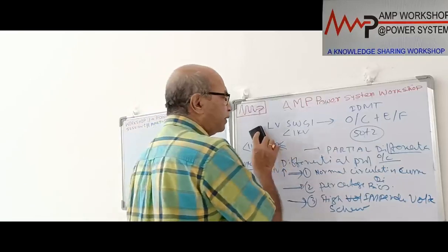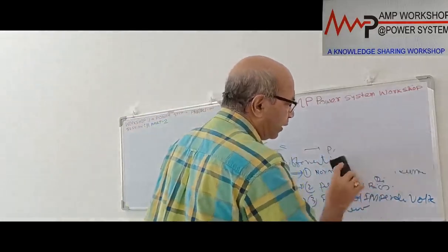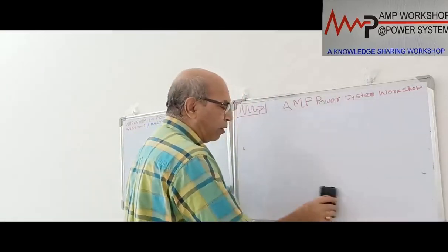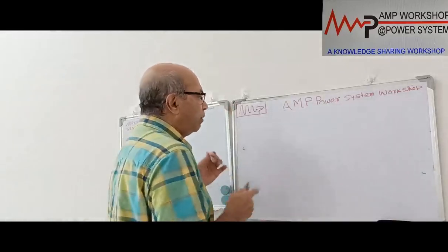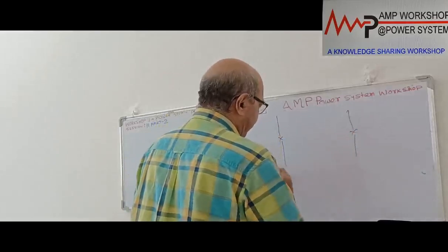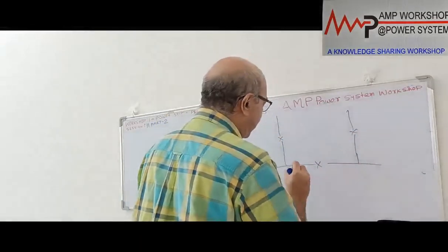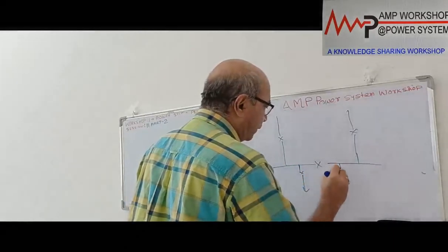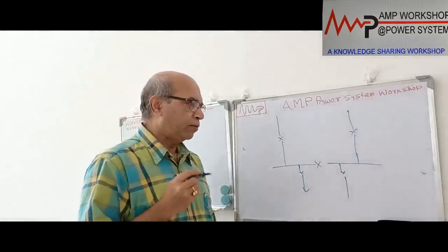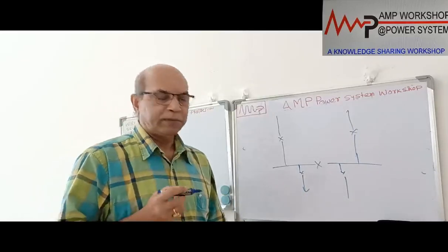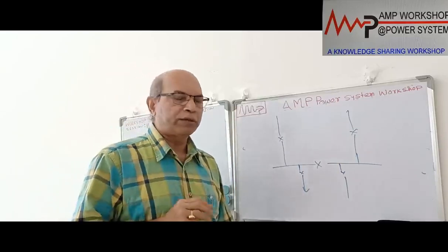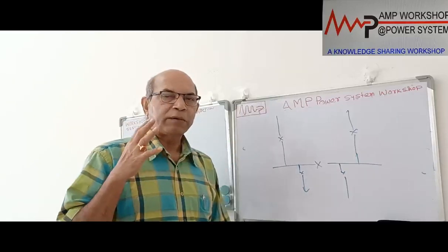So let's start with the first, LV switchgear with overcurrent and earth fault protection. How is this done? This is actually not busbar protection, we have already discussed it during the incomer. Suppose we have 2 incomers and 1 bus section. This is the switchgear arrangement, and various outgoing feeders go from here. In this case, one point we have to discuss going to busbar protection. When you provide busbar protection, we always identify which area of the busbar we are going to protect. So we call it the busbar protection zone.